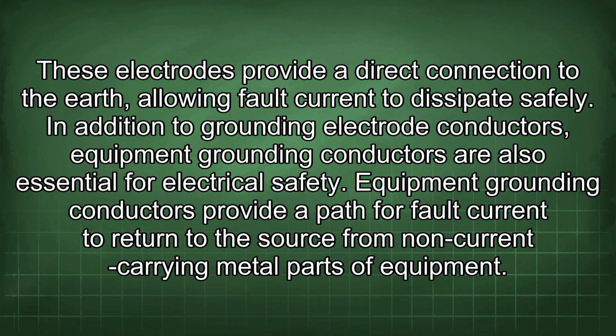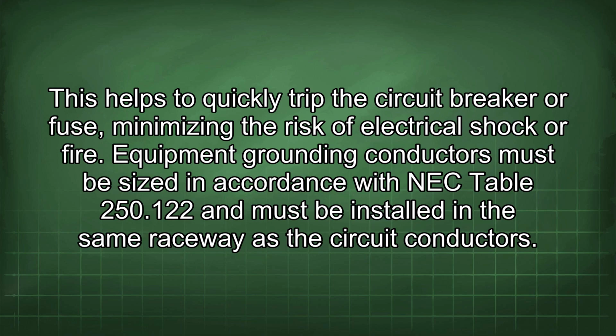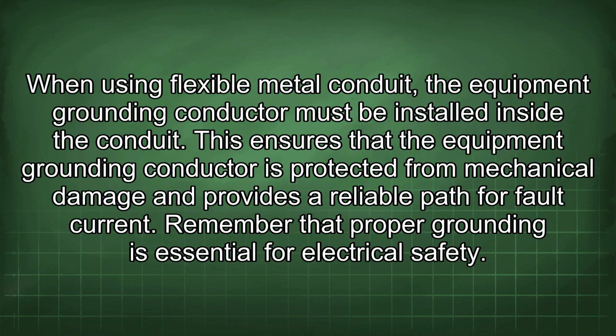In addition to grounding electrode conductors, equipment grounding conductors are also essential for electrical safety. Equipment grounding conductors provide a path for fault current to return to the source from non-current carrying metal parts of equipment. This helps to quickly trip the circuit breaker or fuse, minimizing the risk of electrical shock or fire. Equipment grounding conductors must be sized in accordance with NEC Table 250.122 and must be installed in the same raceway as the circuit conductors. When using flexible metal conduit, the equipment grounding conductor must be installed inside the conduit. This ensures that the equipment grounding conductor is protected from mechanical damage and provides a reliable path for fault current.